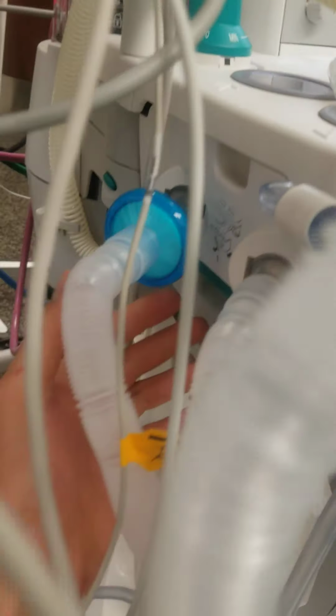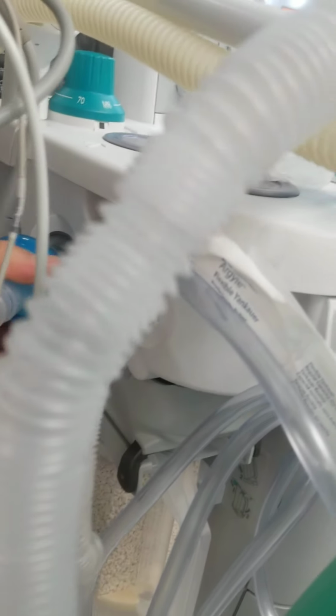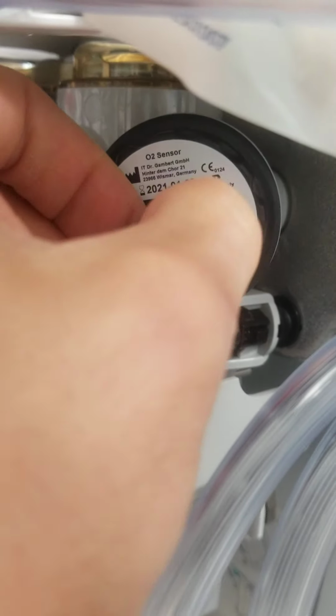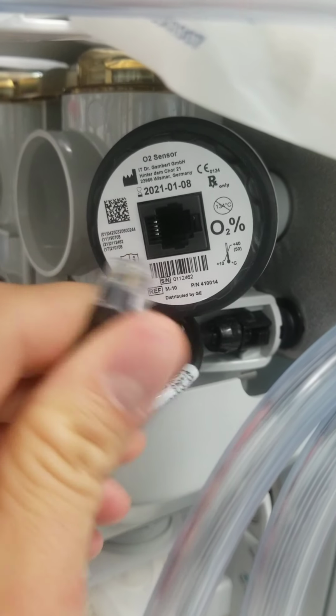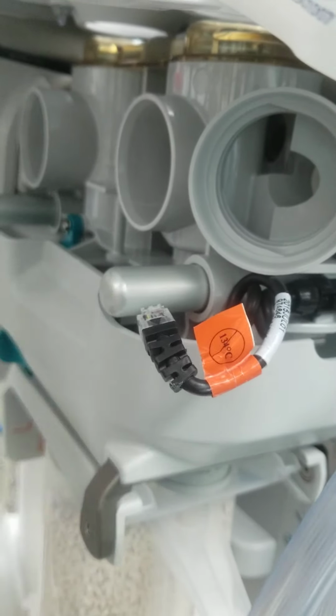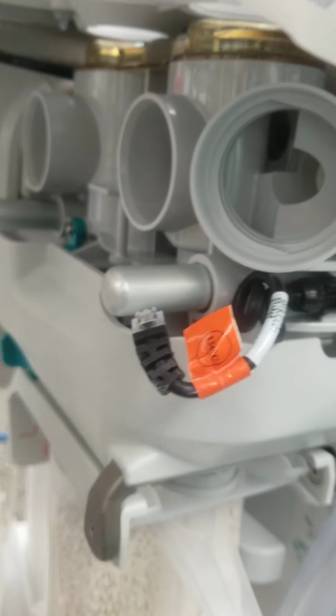So what we're going to do, come down to the flow meters here. We're going to pop this off all the way, like I was saying you could do earlier. Pop this off all the way. You run the risk of, after checking your circuit, you might create a leak because you don't put things back together. So maybe it's better to do this early on. Now with your O2 sensor, you first need to take the wire out, because if you twist the wire, it's going to break. Now twist this out. It's like a screw. Here's your O2 sensor. I make sure that there's no oxygen in it. It's just got room air. I'm going to reattach it. Okay, you just let it hang here. It's hanging in room air.